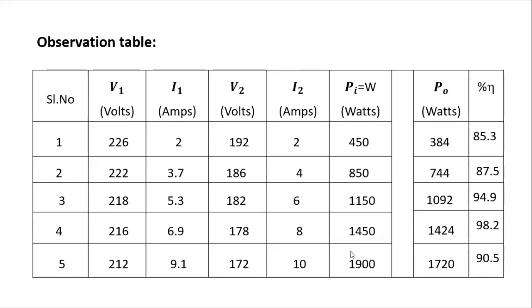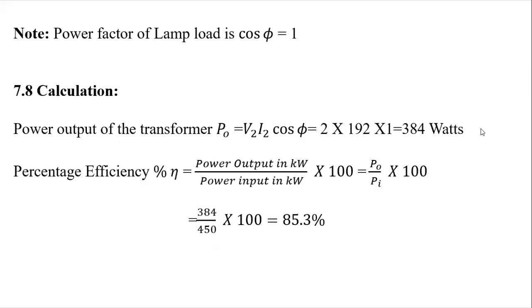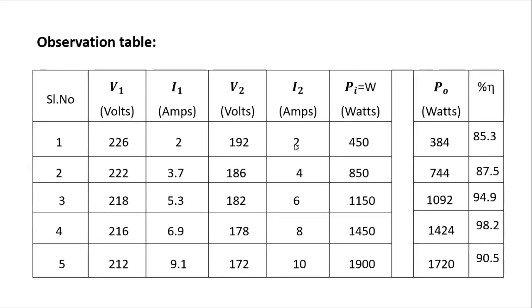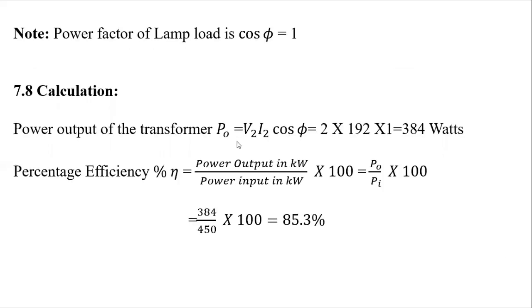For each reading, we are going to calculate the output power and efficiency of the transformer. In order to calculate the output power, the formula is given here: P0 is equal to V2 into I2 into cos phi. Since it is a resistive load, the power factor of the load is taken as 1. I have done the calculation for the first reading here. From the tabular column, you can observe that the current on the secondary side is 2 amperes and the secondary voltage is 192 volts. So that is 2 into 192 into 1, which is 384 watts.